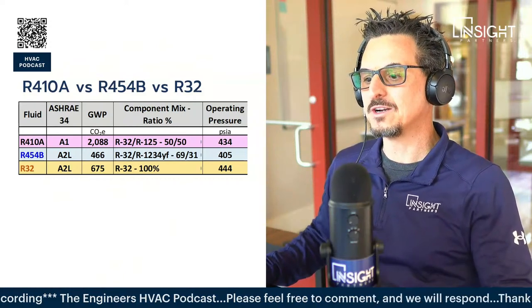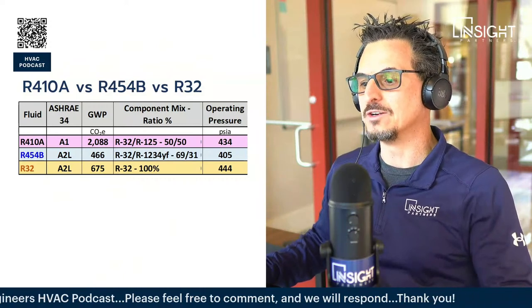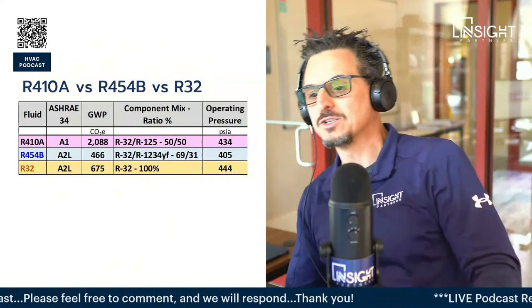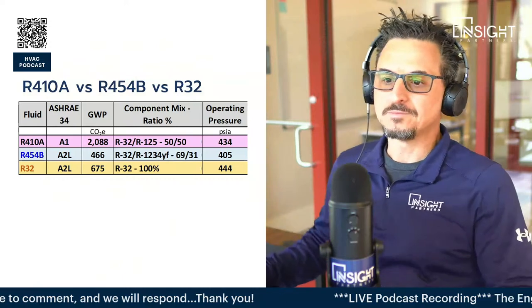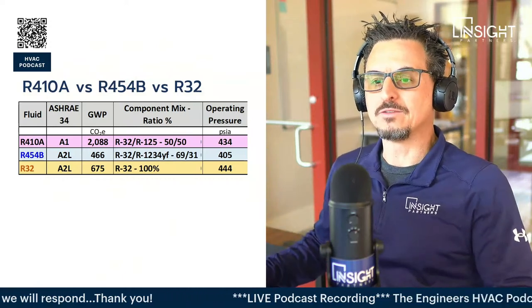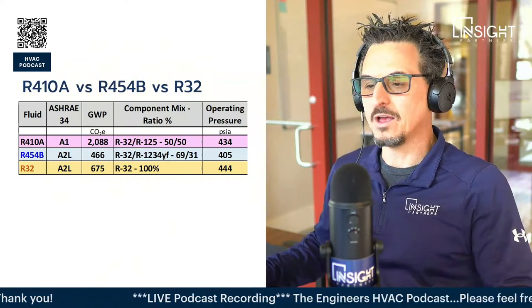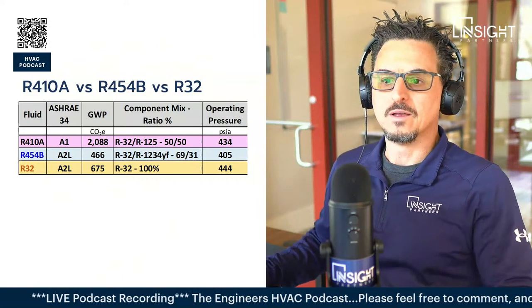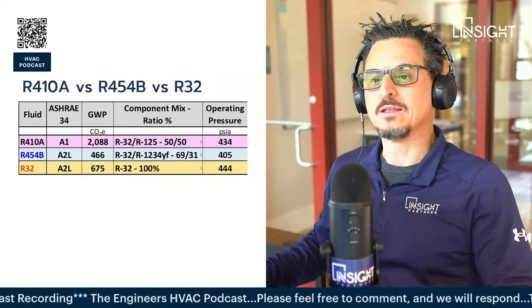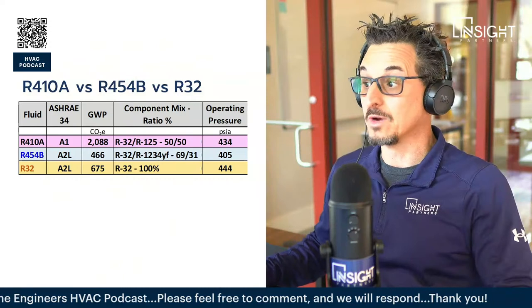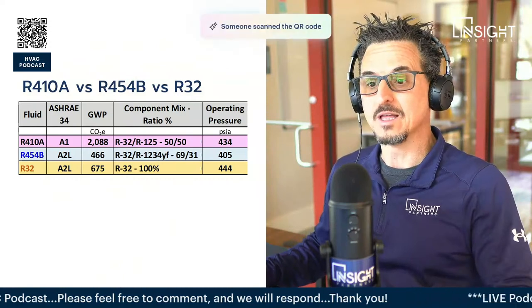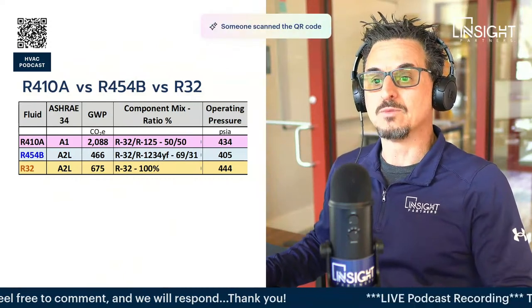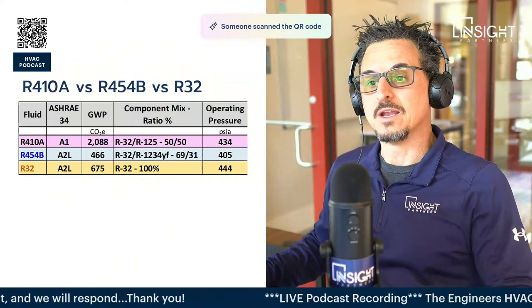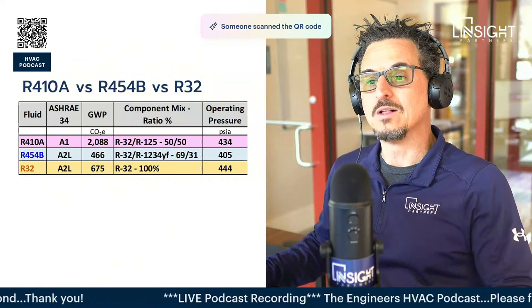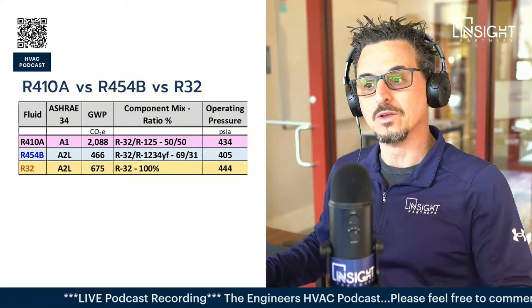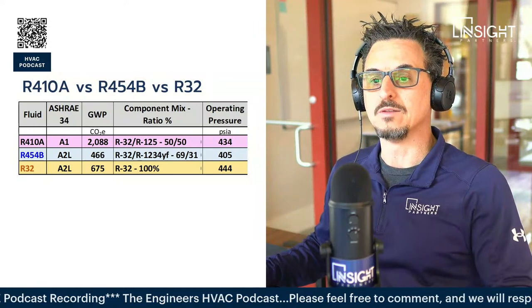Multiple factors to consider: safety, global warming potential, energy efficiency, capacity, pressure, and availability. So if you look at this chart, if you're watching this on our YouTube channel - if you look at the ASHRAE 34 designation, we're going to talk about that in a minute because there's a lot of confusion around that. A1 is what 410A is right now, which is non-flammable. A2L is what is called mildly flammable. We'll look at what that means in a moment.